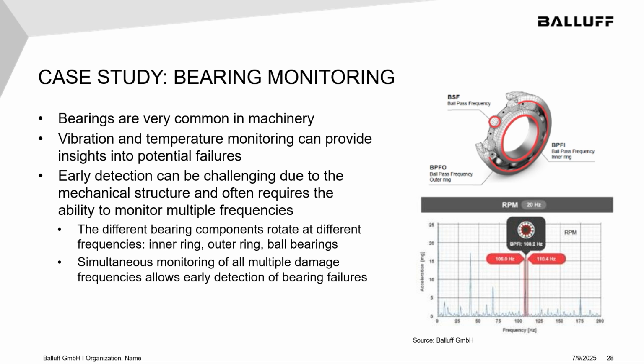What happens with a bearing is you have the inner race that vibrates at a certain frequency, the ball bearings vibrate at a different frequency when they're failing, and then the outer race vibrates at a different frequency. Using a fast Fourier transform analysis, you can break out those different frequencies and monitor those specifically. So breaking that time series vibration data into different frequencies, monitoring those and setting alarms based on them, is potentially a much more effective approach. Not all vibration sensors have this capability, but when you are looking at monitoring bearings, you can find sensors such as the Balluff BCM that allow you to break down those frequencies and detect the failures more quickly.